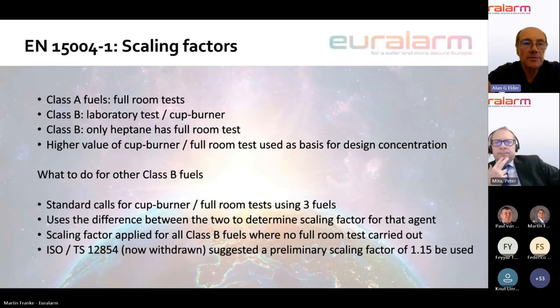The next subject is respecting scaling factors. Now, scaling factors in this context actually only apply to a fairly small part of the market, because what they do is apply to Class B hazards. So if we look at Class A fuels, which are typically those containing electrical equipment, data centers, electrical switch rooms, etc., in order to determine the extinguishing and therefore the design concentrations, we have to do a full room test. So there are a number of tests that are identified within the standard, including wood crib and 3 plastics with repeatability, with certain pass-fail criteria.